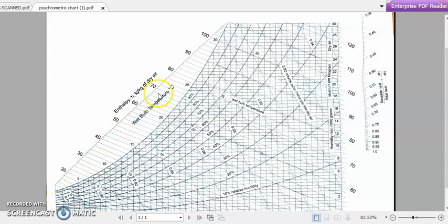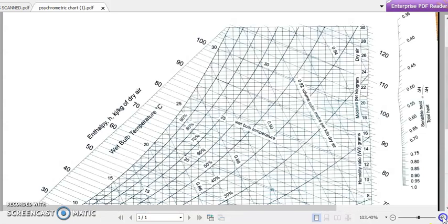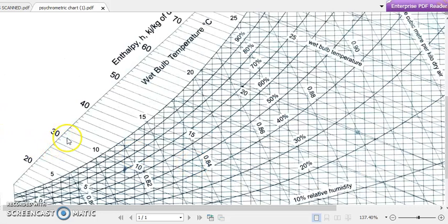The enthalpy axis is represented by h, with values in kilojoules per kilogram of dry air — representing how much kilojoules of heat is present per kilogram of dry air. Values go from 20, 30, up to 100 kilojoules per kilogram. There are inclined lines traveling from the enthalpy axis into the psychrometric chart — these are the enthalpy lines.